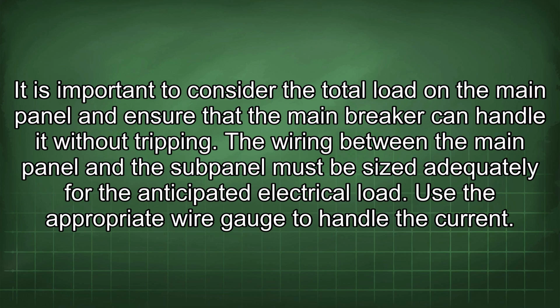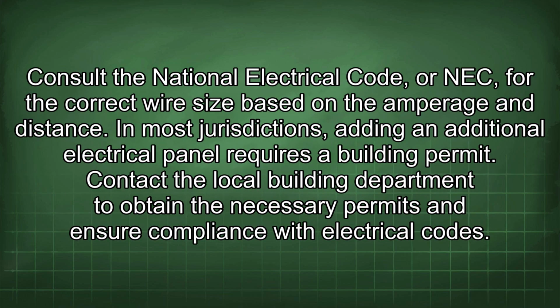The wiring between the main panel and the subpanel must be sized adequately for the anticipated electrical load. Use the appropriate wire gauge to handle the current. Consult the National Electrical Code, or NEC, for the correct wire size based on the amperage and distance. In most jurisdictions, adding an additional electrical panel requires a building permit. Contact the local building department to obtain the necessary permits and ensure compliance with electrical codes.